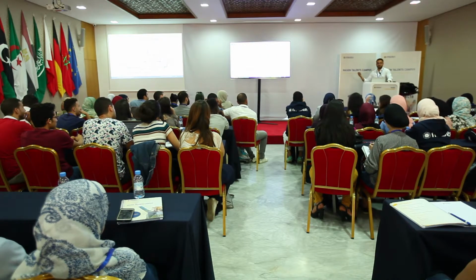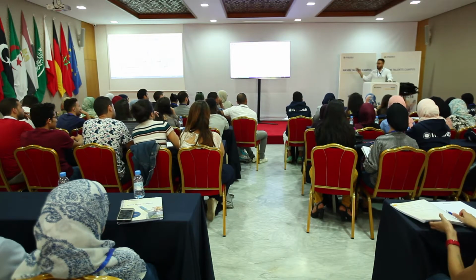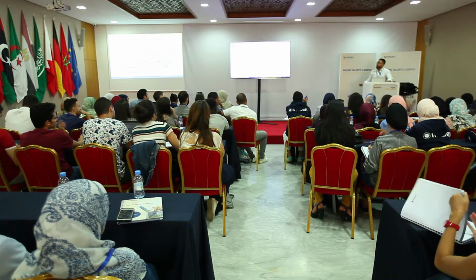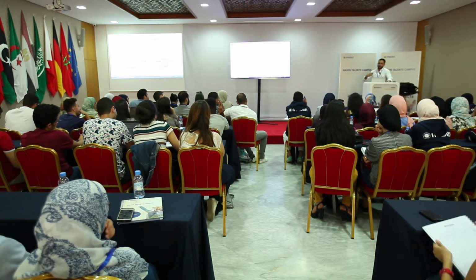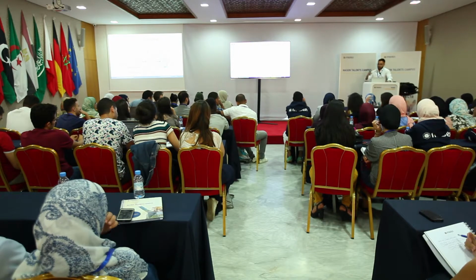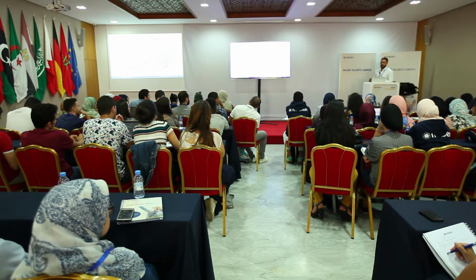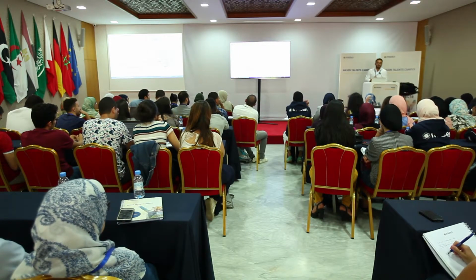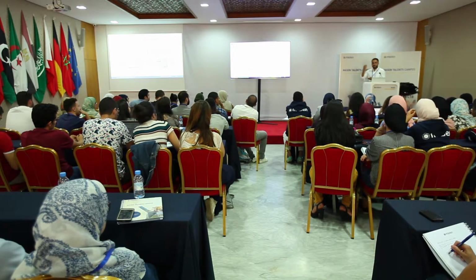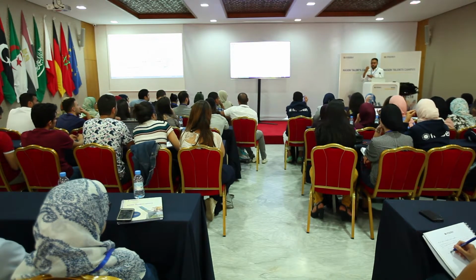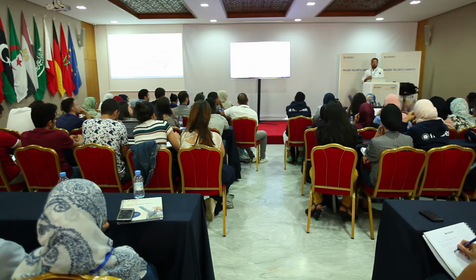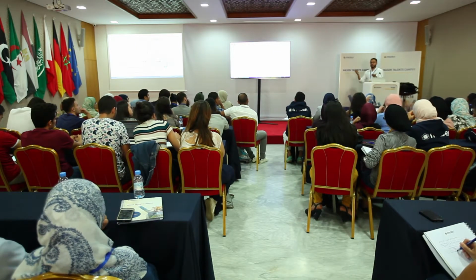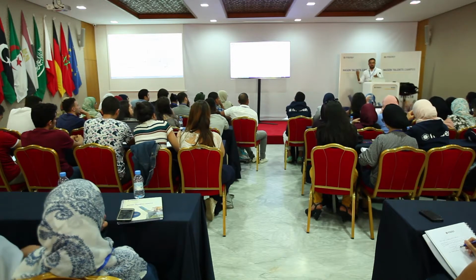The lifetime of troughs is generally 20 to 25. After this period, how can we recycle? Okay. So first, not true. The lifetime of a CSP plant has been proven to be 40 years, and the question mark is even more. The thing with CSP is that the degradation is close to zero, relying on the fact that we do constant maintenance, like for a coal plant that lives 40 years. This is the same. The CSP plant can last the same as a coal plant.